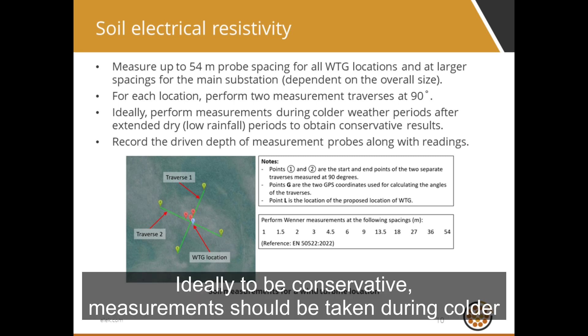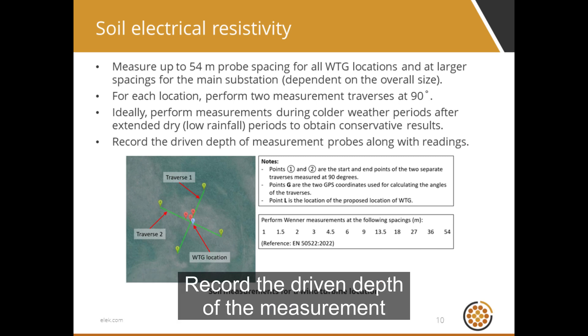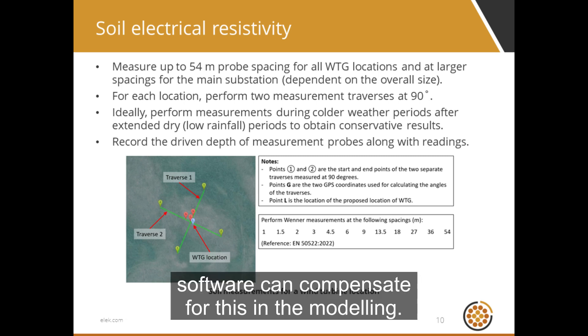Ideally, to be conservative, measurements should be taken during colder weather after extended dry periods, but this may not always, or ever, be possible. Record the driven depth of the measurement probes with the readings so that the software can compensate for this in the modeling.